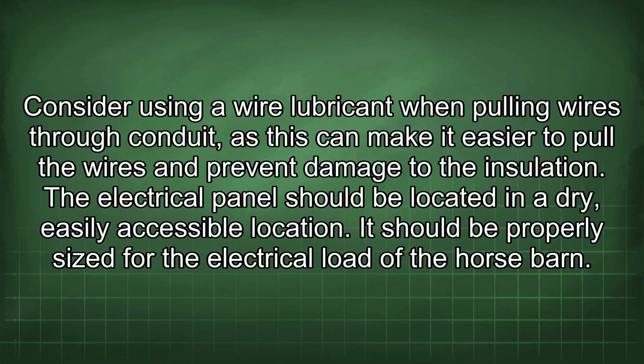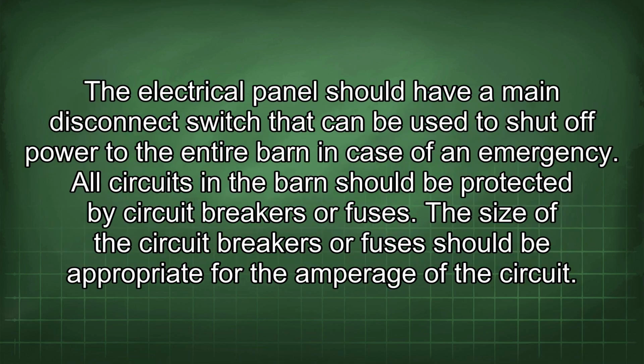The electrical panel should be located in a dry, easily accessible location. It should be properly sized for the electrical load of the horse barn. The electrical panel should have a main disconnect switch that can be used to shut off power to the entire barn in case of an emergency. All circuits in the barn should be protected by circuit breakers or fuses. The size of the circuit breakers or fuses should be appropriate for the amperage of the circuit.